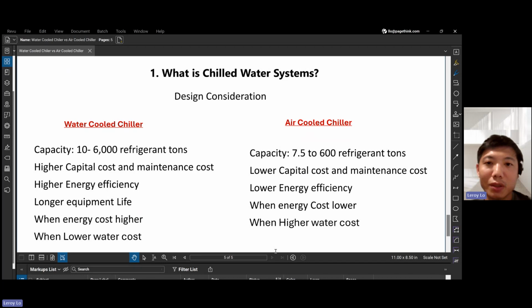And number three will be higher efficiency for water-cooled chillers. Usually they will be more energy efficient because the compressor has to do less work, since water-cooled chillers have lower condensing water temperature and pressures, and it is also based on the thermodynamic law. Whenever you have a larger delta T difference, your heat transfer rate will be higher. So that's the reason behind it. Pretty straightforward. Next, a water-cooled chiller normally has a longer equipment life because they are mostly installed indoors, while an air-cooled chiller is installed outdoors, exposed to the environment and elements. Water-cooled chillers normally have roughly 20 to 30 years of life expectancy. Air-cooled chillers are about 10, 15 to 20 years.